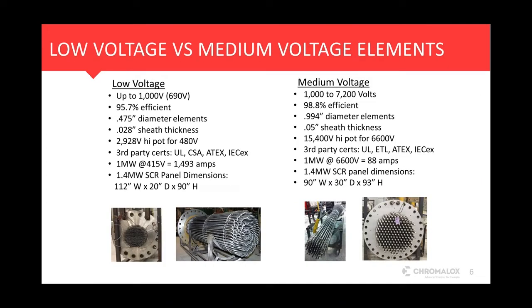So looking at what the electric heating options on the market are, they are not all created equal. Most of what you see on the market would be your low voltage systems, which are rated up to 1,000 volts. But Chromalox has actually developed the first true medium voltage element, which is known as our direct connect systems. And this operates from 1,000 up to 7,200 volts.